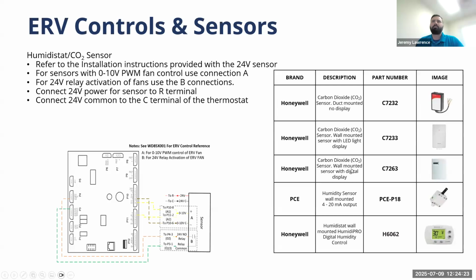Carbon dioxide and humidity sensors are also available to control the space if we found that, or if it was required for your area, and are easily wired in with 2 wires for each terminal to run these systems. They've recently actually simplified these controls and startup. There was a USB Wi-Fi stick that was required for every install, 1 per project, and you'd use that USB stick to program each of the ERVs upon commissioning. They've actually just simplified all these controls, and that's no longer required, which was great news. Also great news because when they incorporated some of these simplifications into the system, it actually came with a price decrease, which is so rarely seen these days. But First Company is committed to bringing these technologies to the market as competitively as possible.